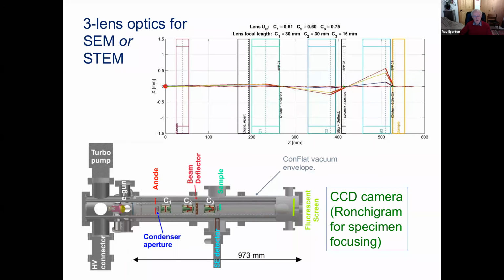Then we have our 3 lenses and a beam deflector to focus the electrons into a small spot on the sample. And of course, a secondary electron detector if you want to do secondary electron images. And in order to adjust the focus, we have a fluorescent screen at the far end of the column, which will form a Ronchigram, an out of focus shadow image of the specimen. That's useful if you want to do fine focusing of the electron beam on the sample.